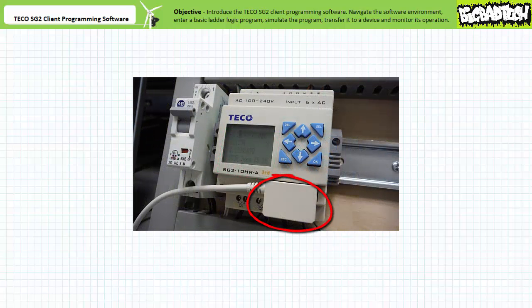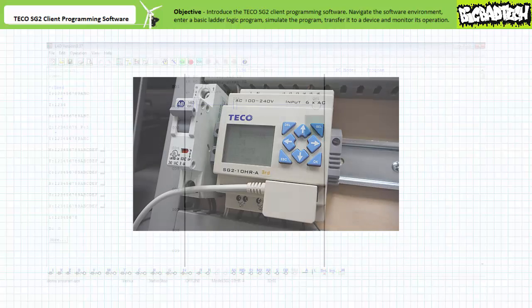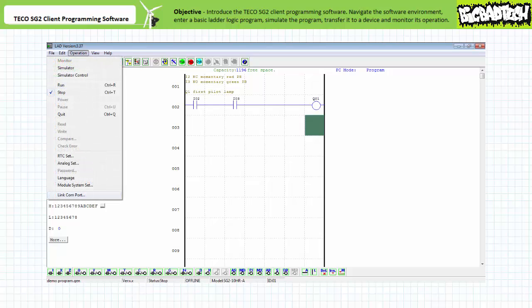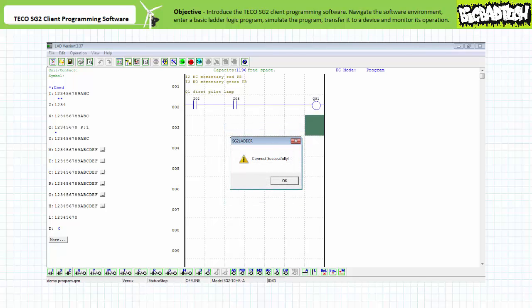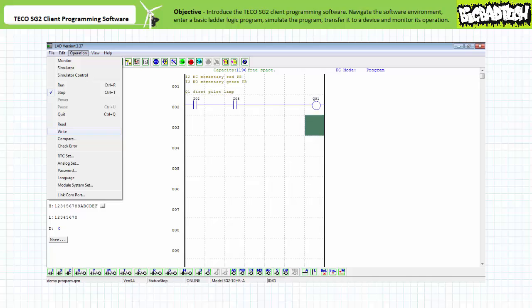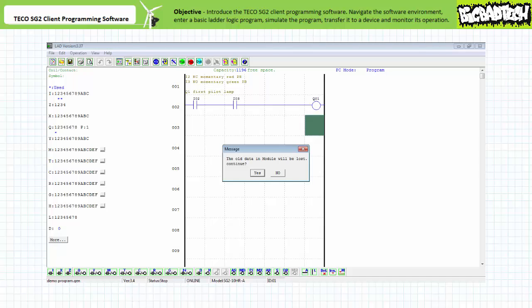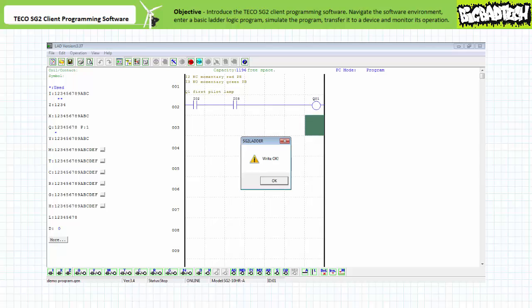Open the port on the front of the device and install the communications cable, plugging the other end into your computer's USB port. Take note of which COM port the computer assigns the communications cable — in this case, my computer is using COM port 5. From the TECO SG2 client programming software, open the operation menu and choose link COM port on the bottom. From the pop-up menu, select the COM port of interest — in this case COM port 5 — and press link. If everything proceeds as expected, you should get a thumbs up that a communications link has been established. Now we need to write this program to our target device. Open the operations menu and choose write near the middle. The software warns that previous data will be overwritten — press OK. You should get a thumbs up that the program has been written to the target device.